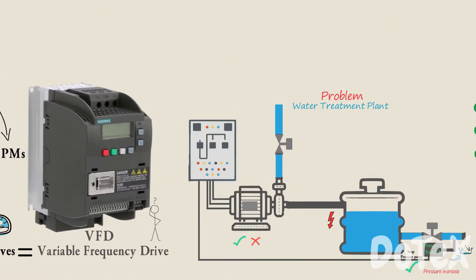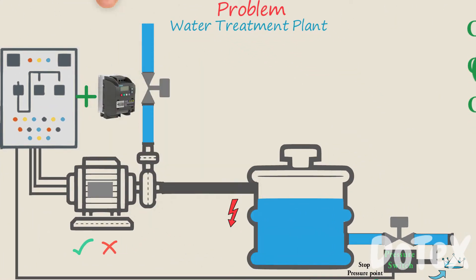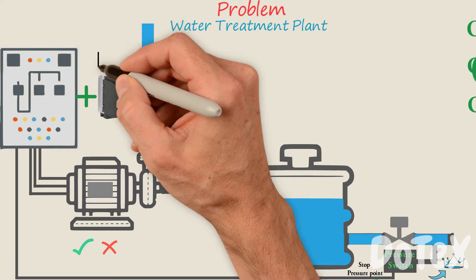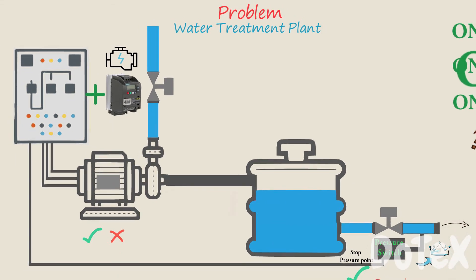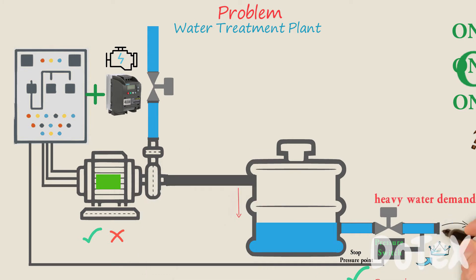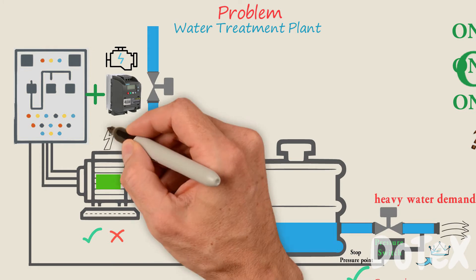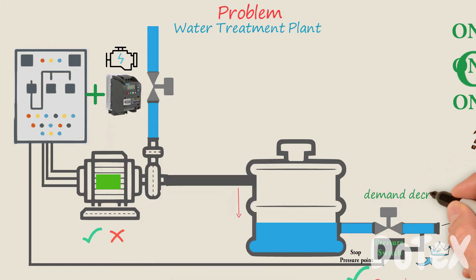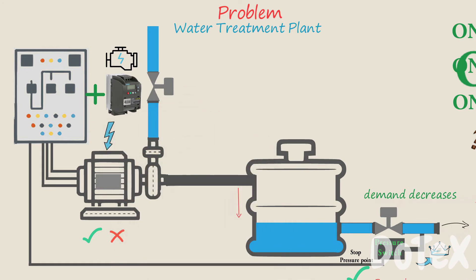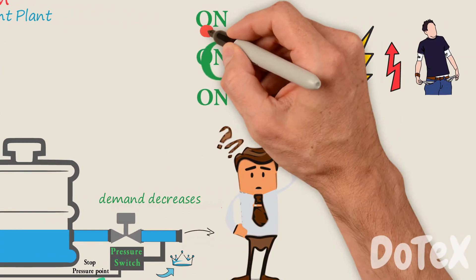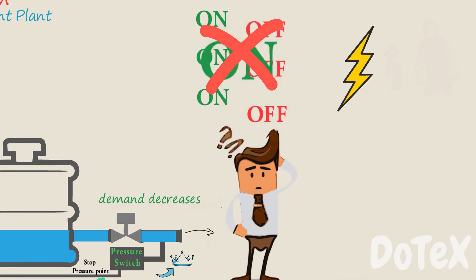Let's go back to our problem. The VFD system will change the speed of the pump in order to keep a constant pressure. When water is used, the drop in pressure turns on the pump. If there is heavy water demand, the pump speed will be higher. As the demand decreases, pump speed will slow or stop. So as you can see, the pump will not start and stop as many times with the VFD system, and this will decrease power loss and save energy and money.